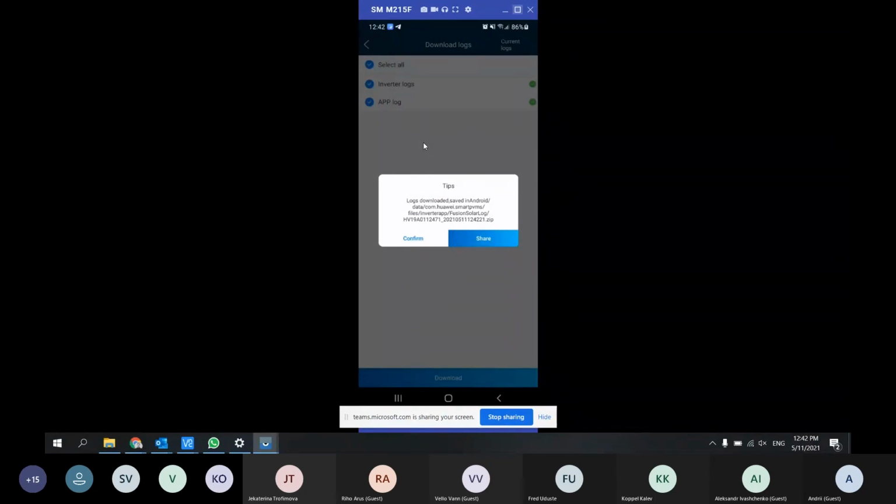So what you need to do, again, measure the voltage AC, DC, and show support that it's okay, the voltage is normal, and then show a video where you connect everything to the inverter, switch on the DC switch, but then nothing happens. So it means that, again, the inverter is faulty. So even if you cannot download the log in this case, you can always prove that the voltage is okay, the DC and AC, but it is not possible to connect to the inverter.